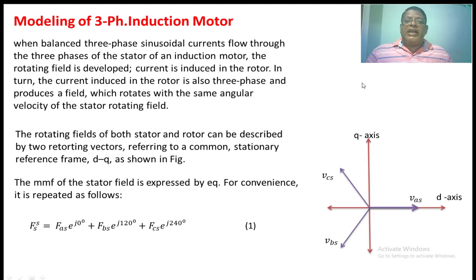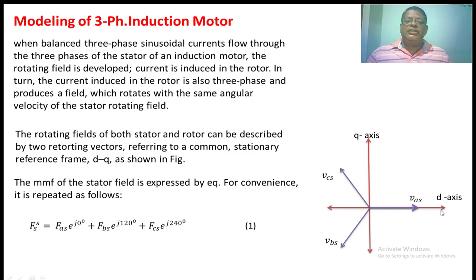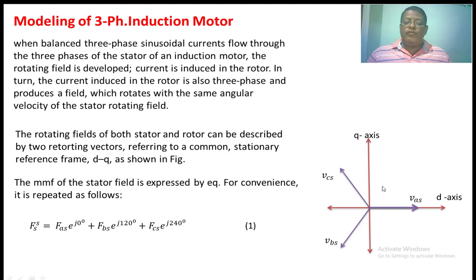We can represent both stator flux and rotor flux in a common stationary reference frame — that is the DQ frame. The D-axis is the axis passing through the rotor field or rotor flux. Perpendicular to the D-axis is the Q-axis. The voltage vector, which is the stator voltage vector VAS, VBS, VCS, are mutually displaced by 120 degrees in space.